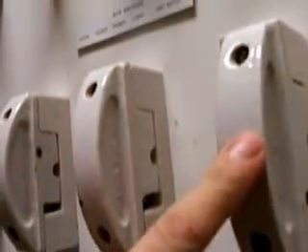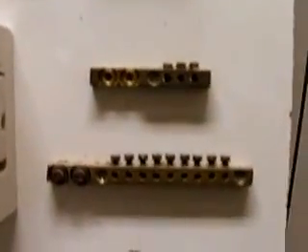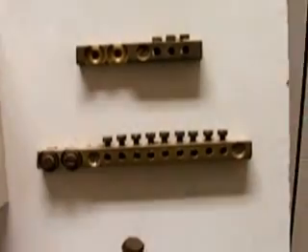Gives you a view of the holder, and again, this is pretty obvious why they got rid of them, because there's not much protecting you if you bugger up and the top of that fuse is live. They used to have a standard where the top of the fuse holder was the live bit, because nothing could fall into it, and if it's a standard system, then yeah, you knew that the top was always live. If I'm wrong, correct me, but that's what I've always understood. And plug that in. And these are all rated at 415 volts, 20 amps each.